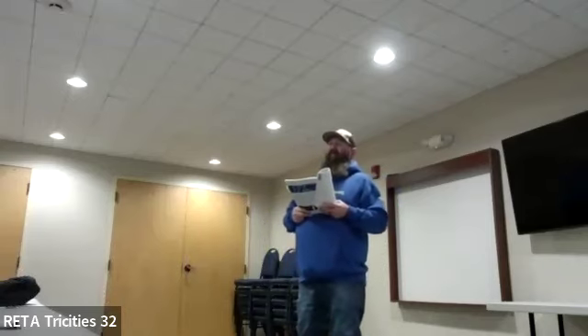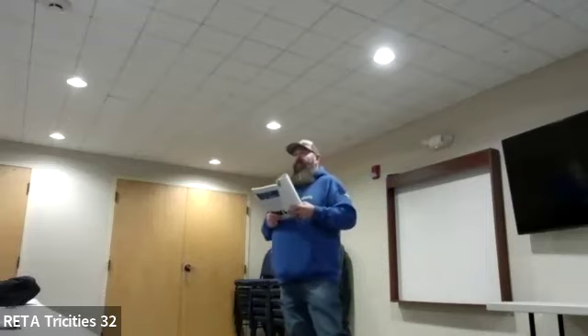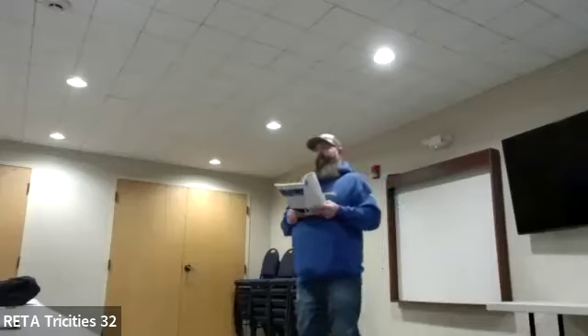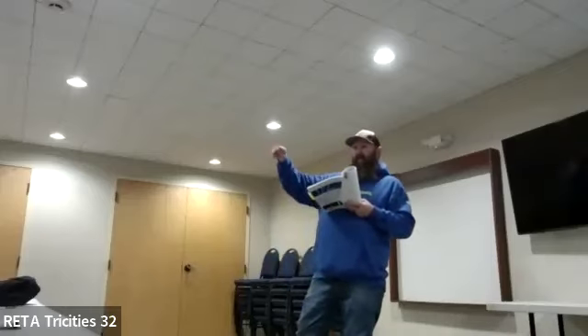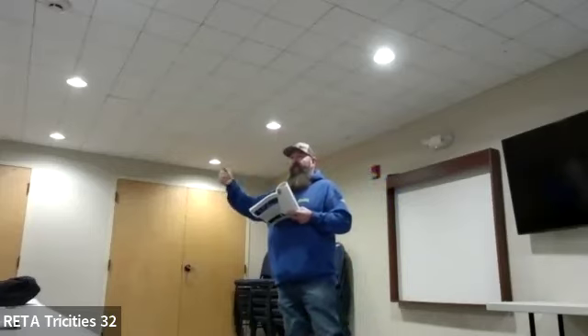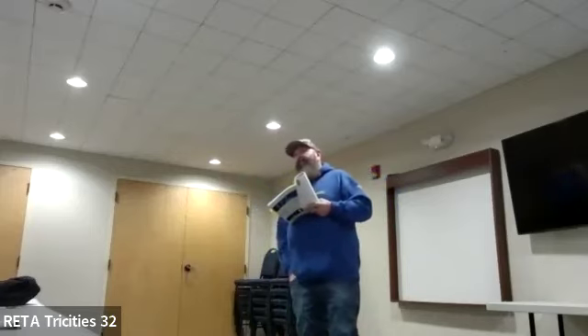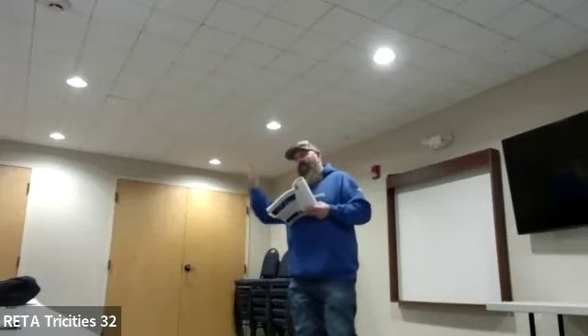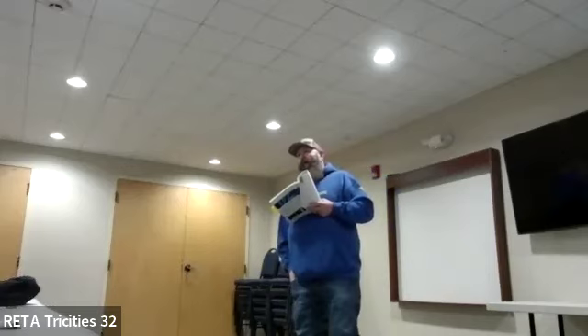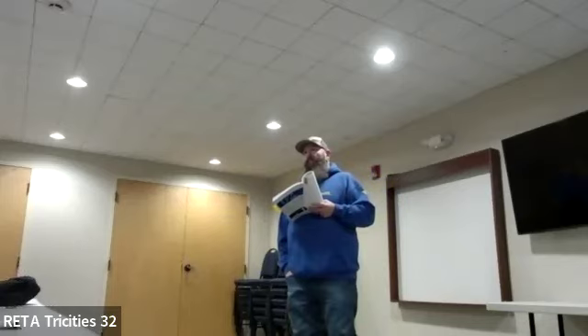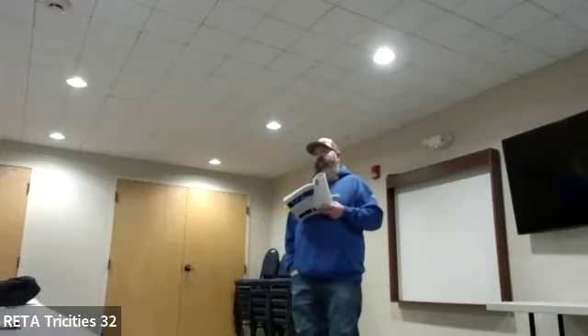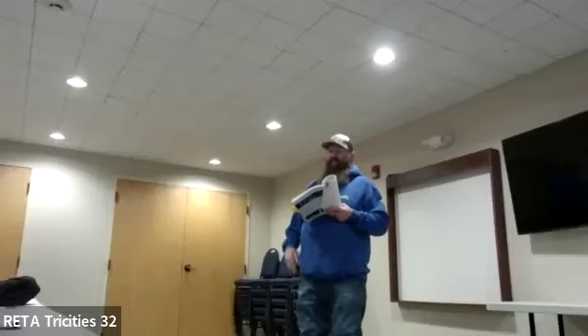Are you giving guidance, like each plant's a little different, or do they have a set standard, out of curiosity? What do you mean, the set point? Yeah, or do you turn that down on the Johnson controls? I'm just throwing that out. So we adjust the temperature range of the room to fire the fans. But as far as conditioning the room, that's left to the facility. Our test is to ensure that the room is going to be below 104. That's the whole idea. 104 degrees, that's the code. That's what we need to be below. Makes good sense.